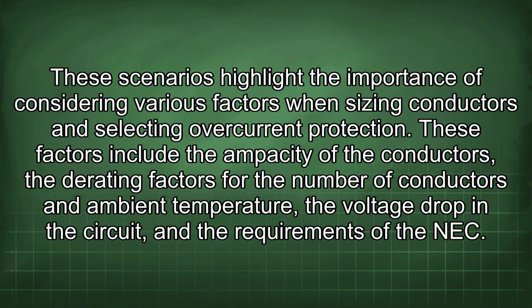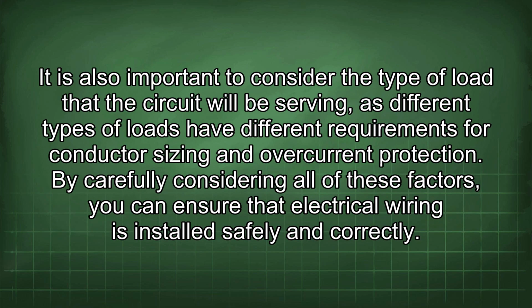the NEC. These scenarios highlight the importance of considering various factors when sizing conductors and selecting overcurrent protection. These factors include the ampacity of the conductors, the derating factors for the number of conductors and ambient temperature, the voltage drop in the circuit, and the requirements of the NEC. It is also important to consider the type of load that the circuit will be serving, as different types of loads have different requirements for conductor sizing and overcurrent protection. By carefully considering all of these factors, you can ensure that electrical wiring is installed safely and correctly.